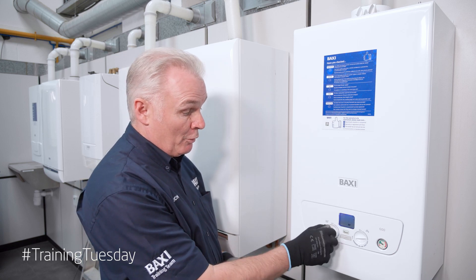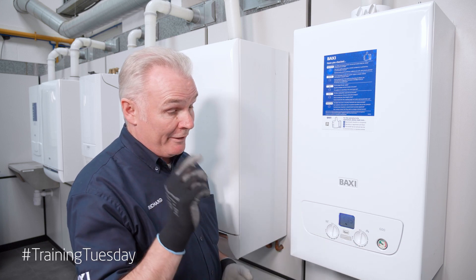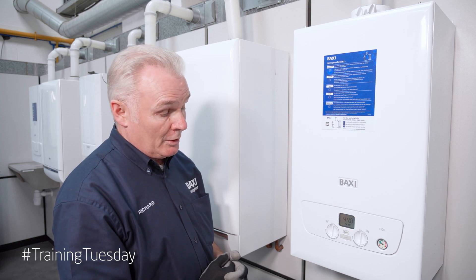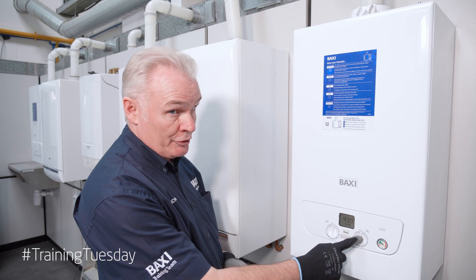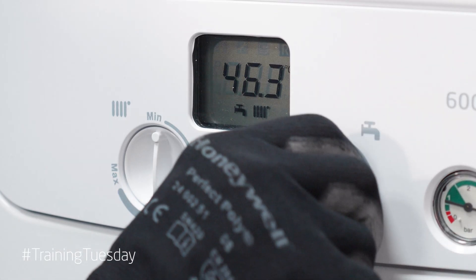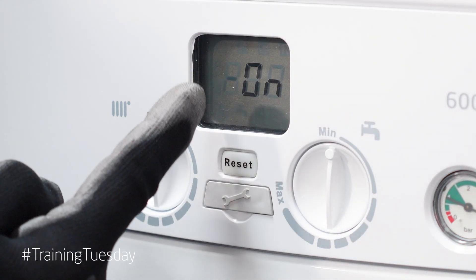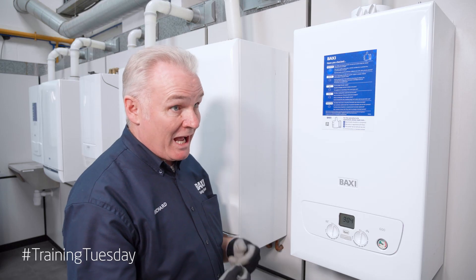Simply turn both control thermostats down to the minimum setting. We wait for a second until it comes back to the front screen showing temperature. Once we're in that position, we go to the hot water thermostat and we do two quarter turns to three o'clock and back — so simply down, up, down, up. If we've done it correctly it will say on 304. This is our chimney sweep setting activated.